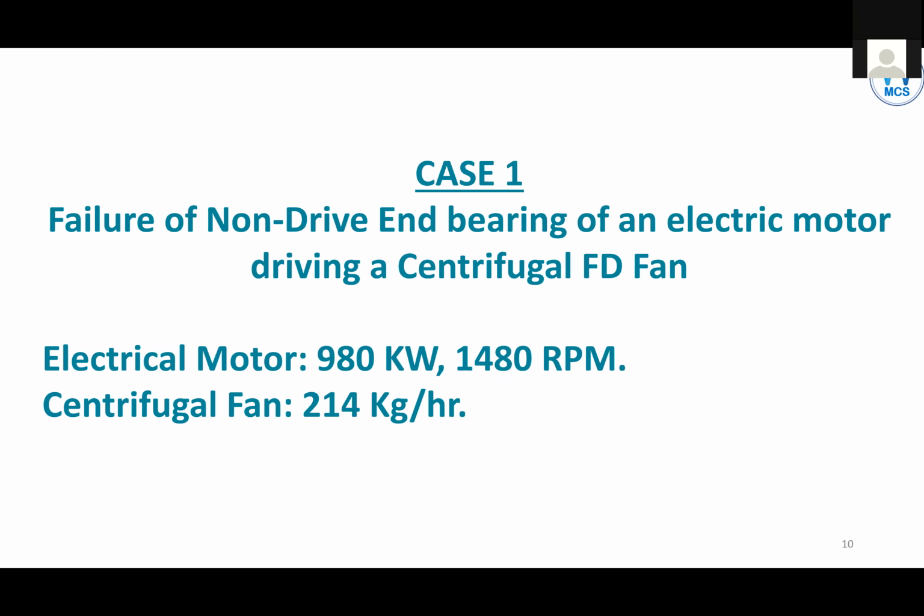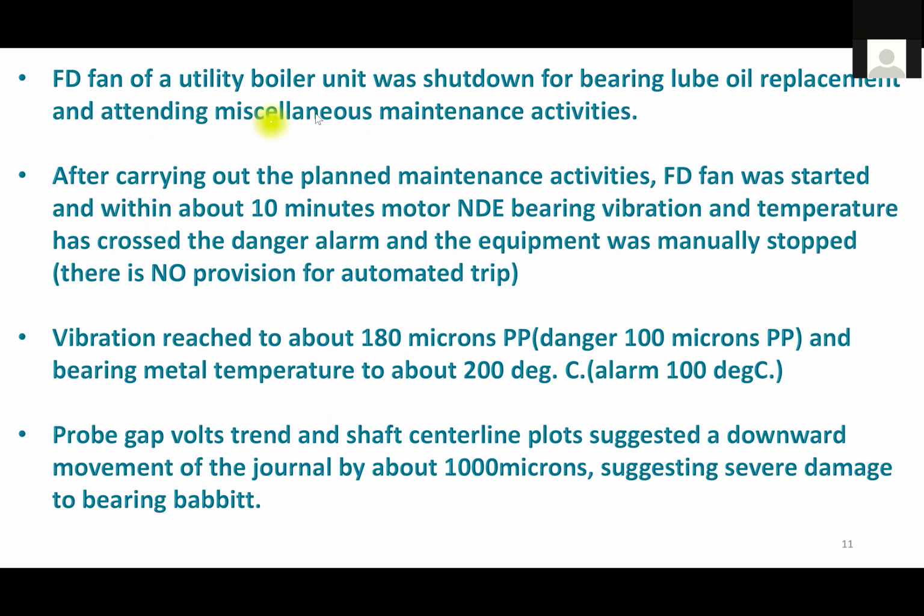So this first case is related to the failure of a Non-Drive End (NDE) bearing of an electrical motor which was driving a centrifugal fan. The brief information is this is an FD fan of a utility boiler unit, and it was shut down for some bearing lube oil changes and attending some miscellaneous maintenance activities. After carrying out the planned maintenance activities, the FD fan was started, and within about 10 minutes, the motor NDE bearing vibrations and temperature crossed the danger level, and the equipment was manually stopped. Actually, there was no provision for automated trip, so the operator had to intervene and trip the machine.